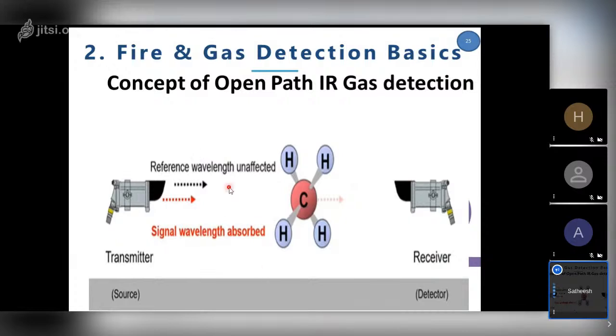It will just say there is a gas leak, for example, a small concentration compared to a big leak, and the detector cannot distinguish between them. Whatever absorption it sees around this area, it is able to report. It cannot say exactly what concentration. So this is more of a leak detector or abnormal alerting device, not like the point gas detector, which is very accurate because the gas comes inside and we close the complete thing, so it is able to see a known volume of gas. But here, it's a big challenge. So it is only to alert that there is a gas leak from this side to that side.